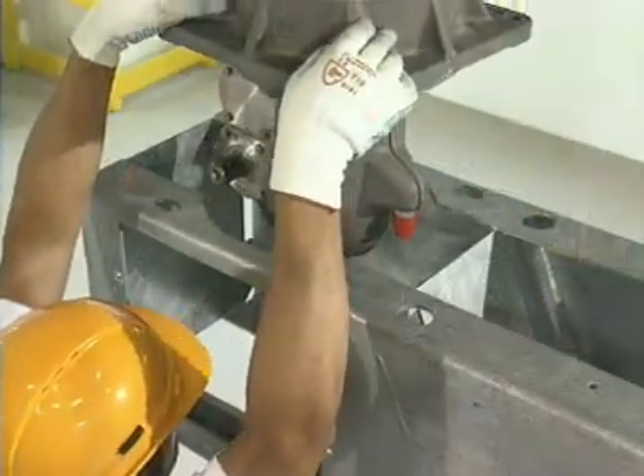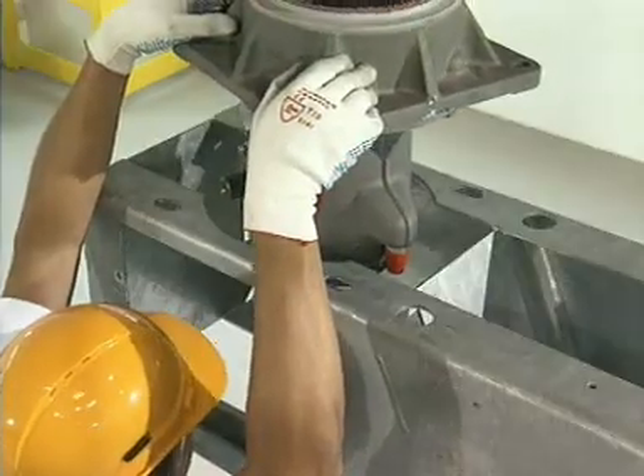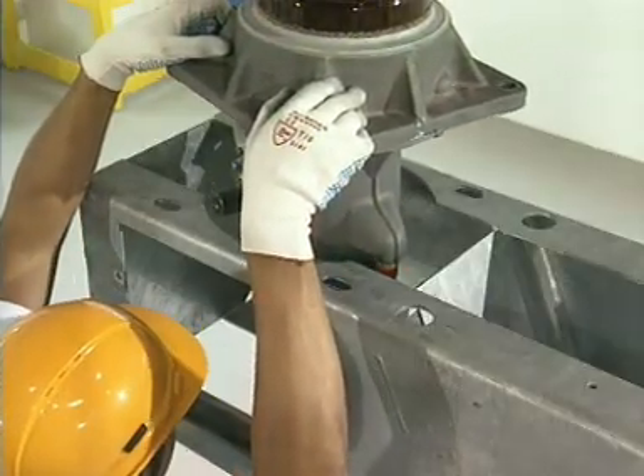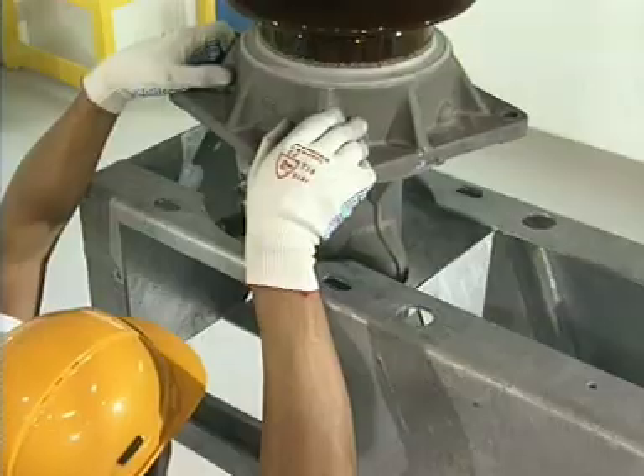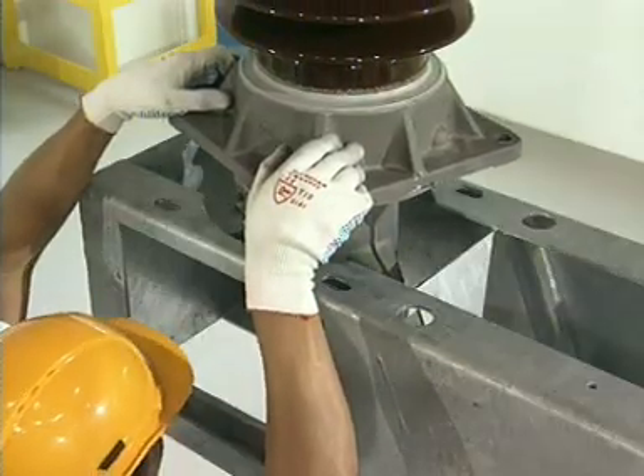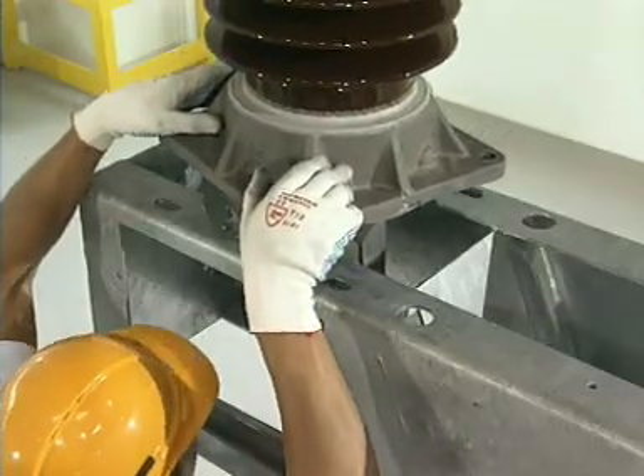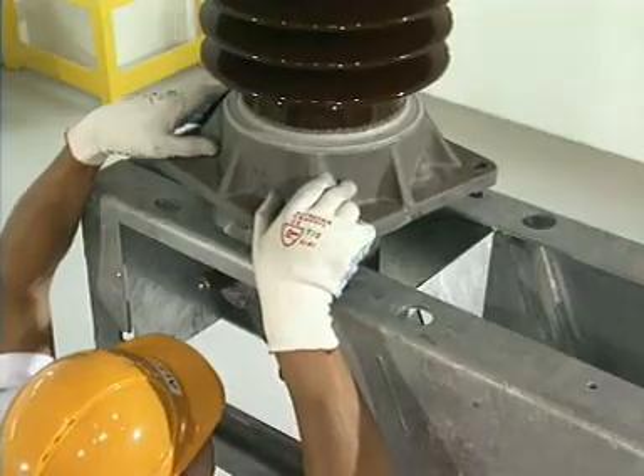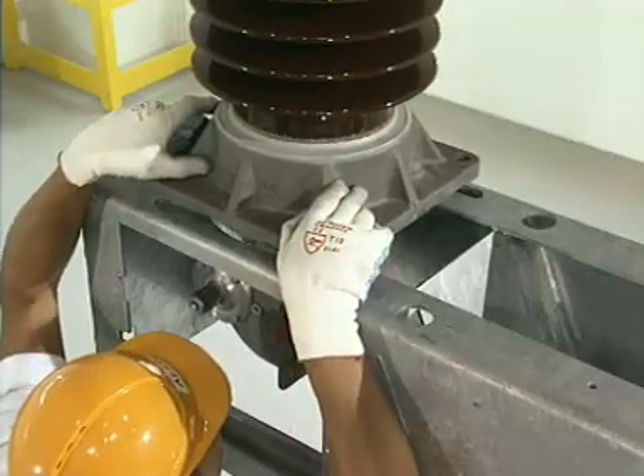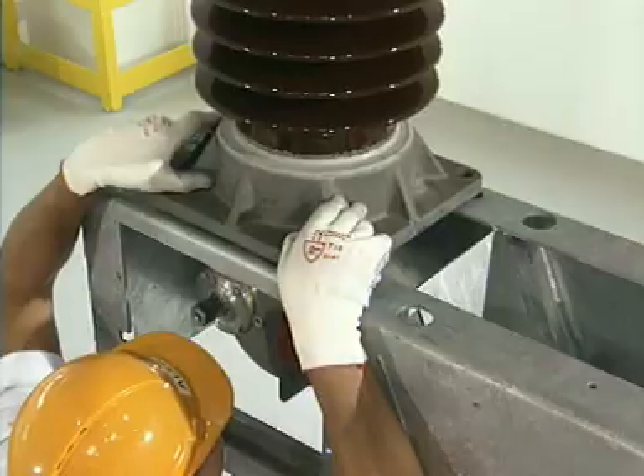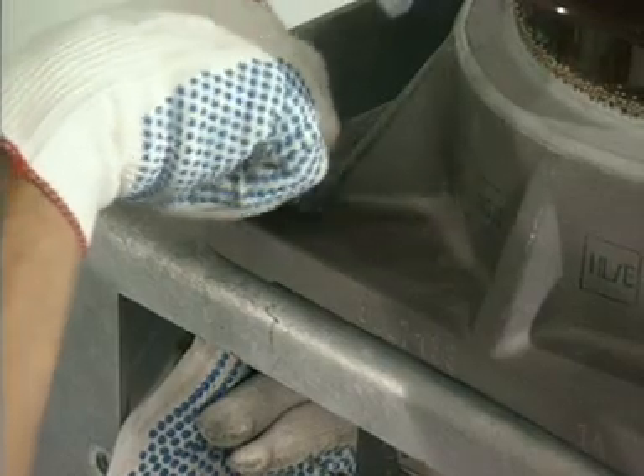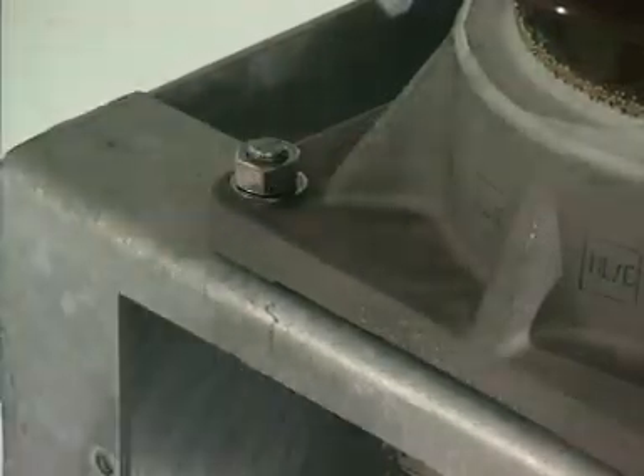Lift the new pole column above the installation opening in the base frame, rotate it approximately 30 degrees from the mounting position and lower it carefully until the torque shaft is completely inside the base frame. Rotate the pole column back to the mounting position, lower it almost completely and secure it with bolts. Do not tighten the bolts yet, since the pole column still needs to be aligned.